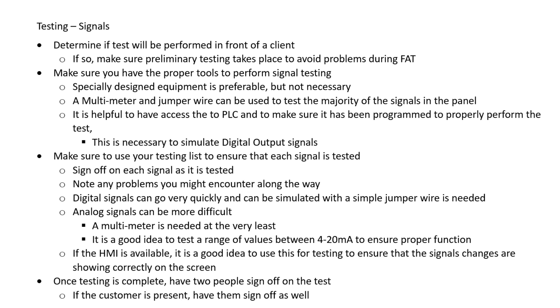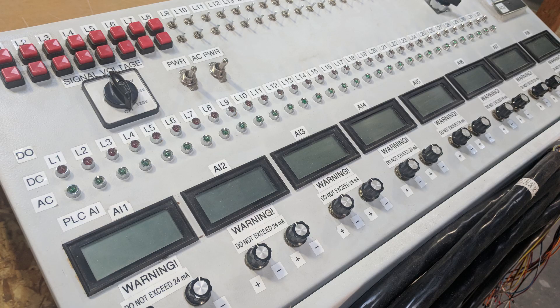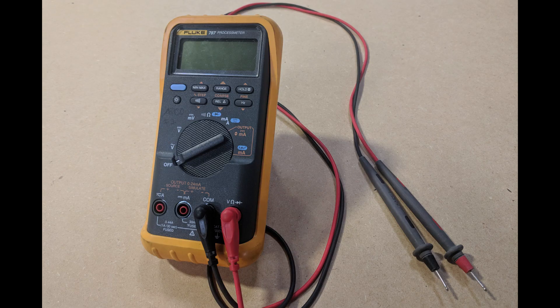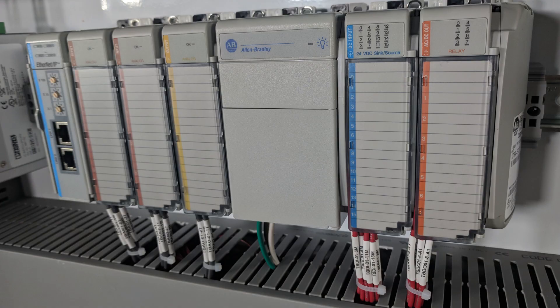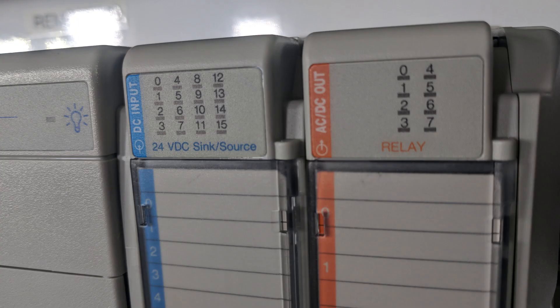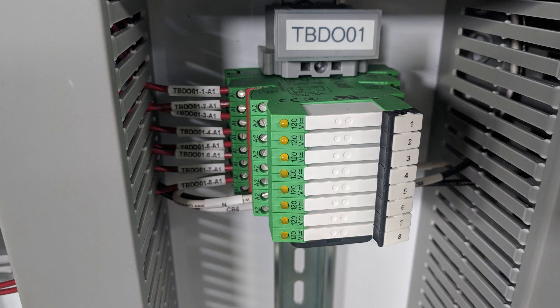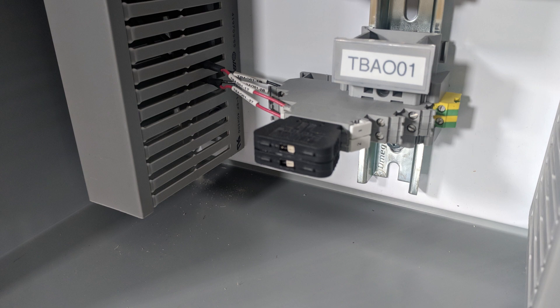We also want to make sure we have the right tools in place for these signal tests. In a lot of cases, specifically designed equipment should be used, but it's not always necessary. In most cases, you can simply use a multimeter and a jumper wire for the digital inputs. It's also helpful to have access to the PLC via a laptop so we can verify it's programmed correctly and simulate digital output and analog output signals.